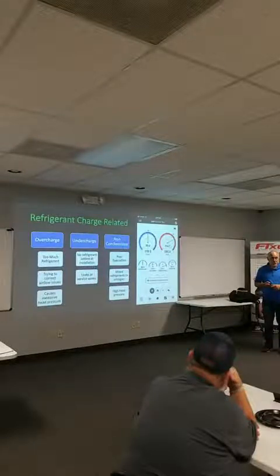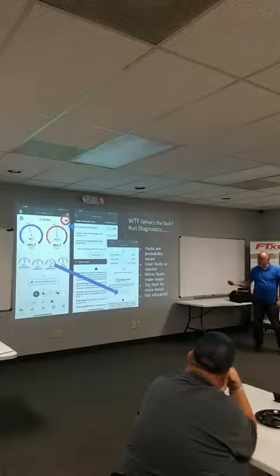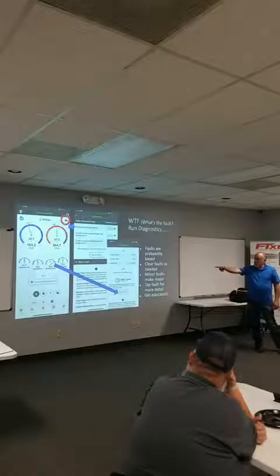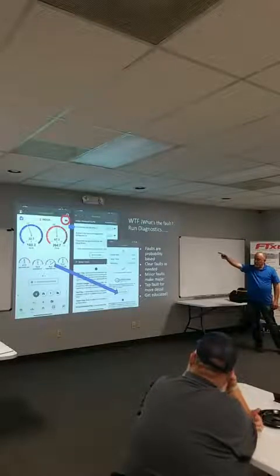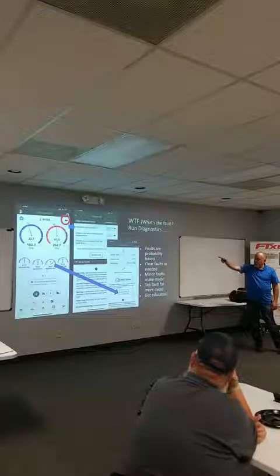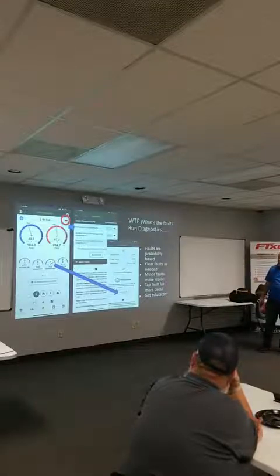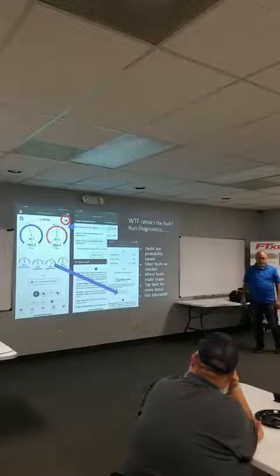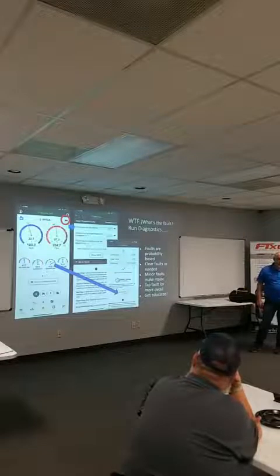Right, so I don't know what they're doing with the property now. It's a disaster. They still ended up buying it, but this is the kind of thing we've got to watch for. Measurequick, when you're running a scan tool here, it does have a flag at the upper top. If you touch that flag, it's going to pull up what's major potential faults. Now I want you to notice the verbiage in here. It says condenser may be dirty. Measurequick was never designed to replace a technician.